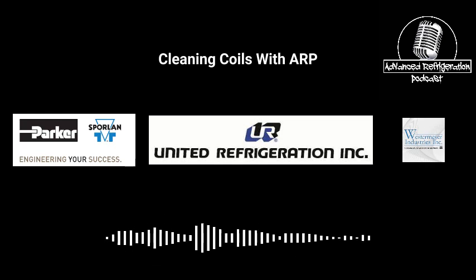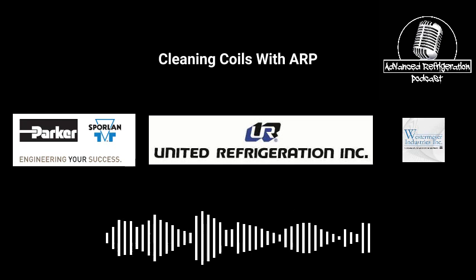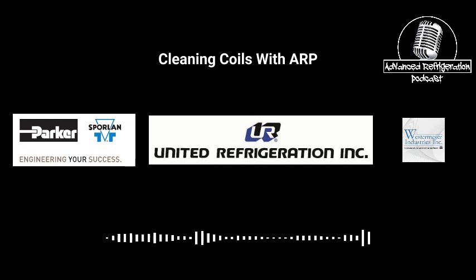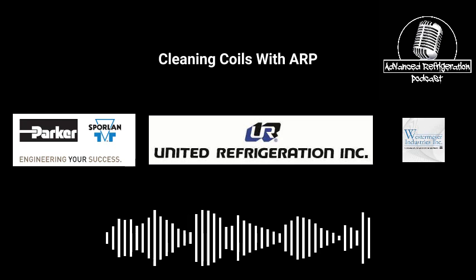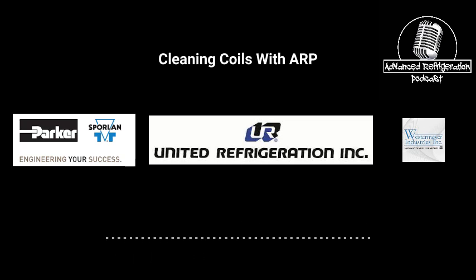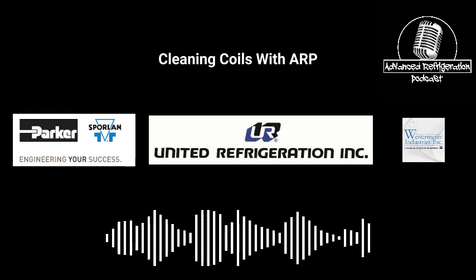A 4 fanner takes that long, but if you get an 8 or a 10 or a 12 fan, it's going to probably take 2 guys an hour to an hour and a half to get it all taken apart and cleaned and assembled back together. So what I like to do is get the coils wet down, and I'll get all the big debris off the bottom, spray it at an angle, then I'll spray it on the top. And then if it needs chemicals, it's going to get chemically cleaned.